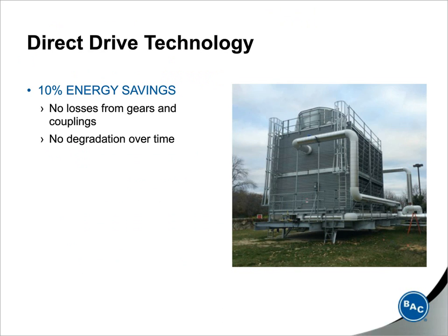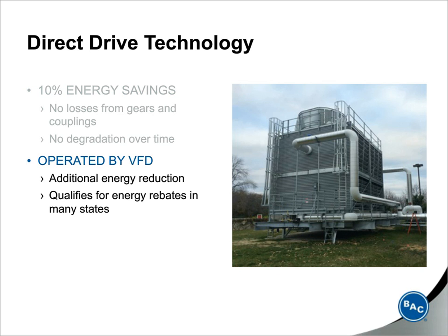Since there aren't any mechanical losses or mechanical degradation that I just spoke about in the last slide, energy usage can actually be reduced by up to 10% versus traditional belt or gear drive systems. And then also, since this is operated by a VFD, direct drive systems are always going to be operated on a VFD. This is going to provide additional energy reduction throughout the year and is going to help qualify for energy rebates in many states.